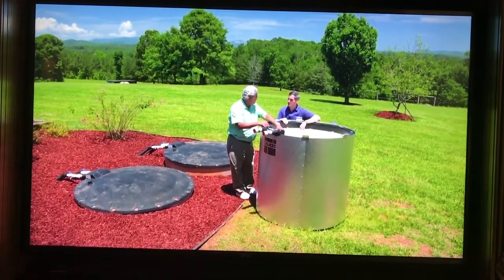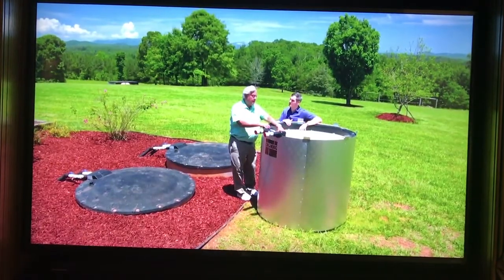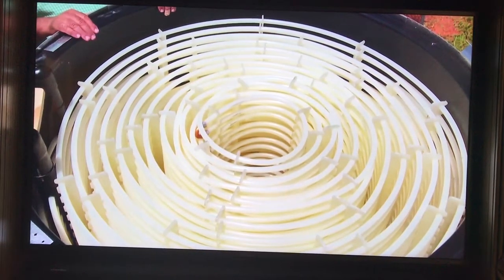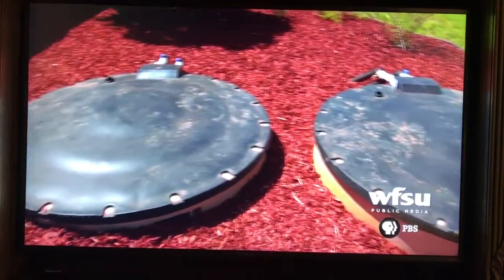Got it. But you're also doing this with the cold tank, right? That's correct. What we do with the cold tank is the cold glycol comes in, goes through the tubes, and we'll make a 500-pound block of ice. Really? Inside, that's right. We'll use that tank at night to keep the house cool. So even when the sun's not shining, you're not running your equipment, your chiller. It's completely off. You have a block of ice to pull all that cooling energy from. Absolutely. Wow, that's fascinating stuff.